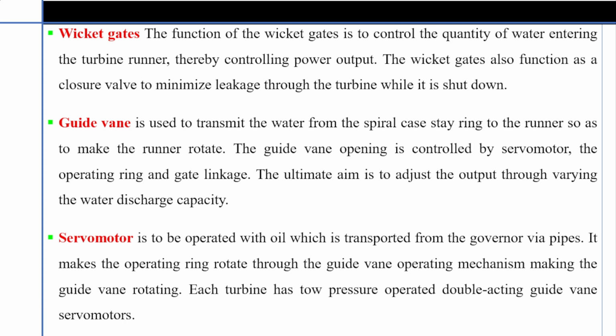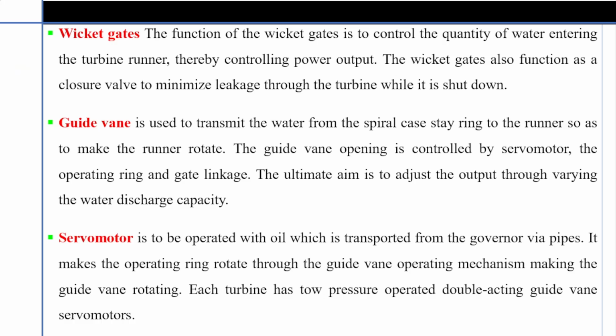The wicket gates also function as a closure valve to minimize leakage through the turbine while it is shut down. Guide vane is used to transmit the water from the spiral case stay ring to the runner so as to make the runner rotate. The guide vane opening is controlled by servo motor. The operating ring and the gate linkage.